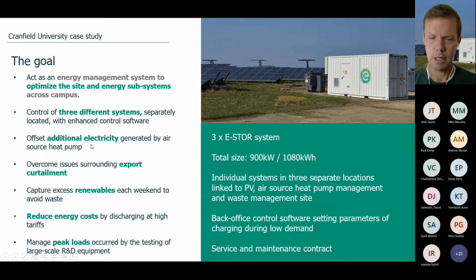One of the primary goals is to offset the additional electricity generated by the air source heat pump. We have metering and data on the heat pump, so we can see when it's being used and how the battery storage system offsets against that. This site is a zero export site, so we overcome those issues by capturing as much solar in the battery as possible and then putting that into the site load, and we've got the data to verify that.